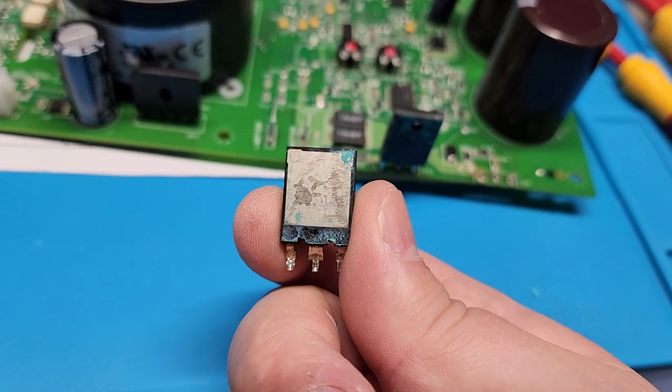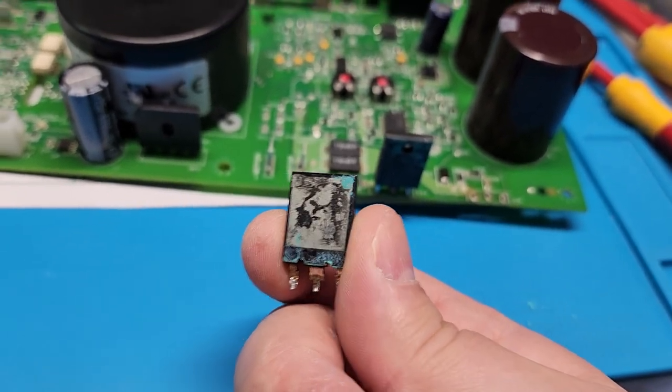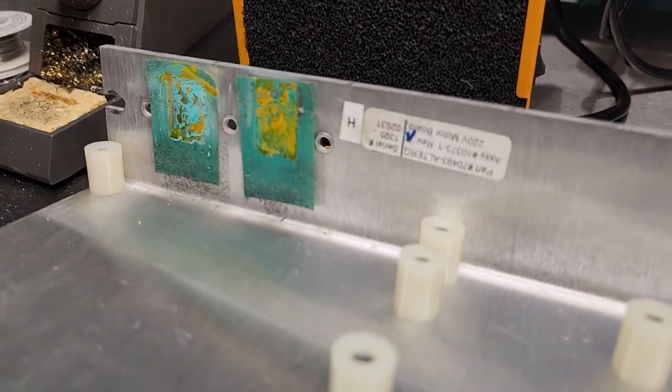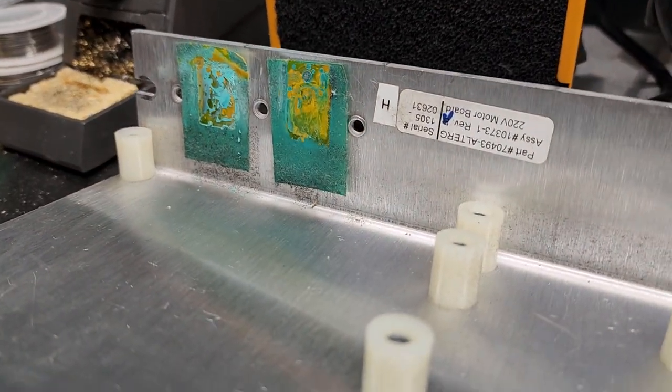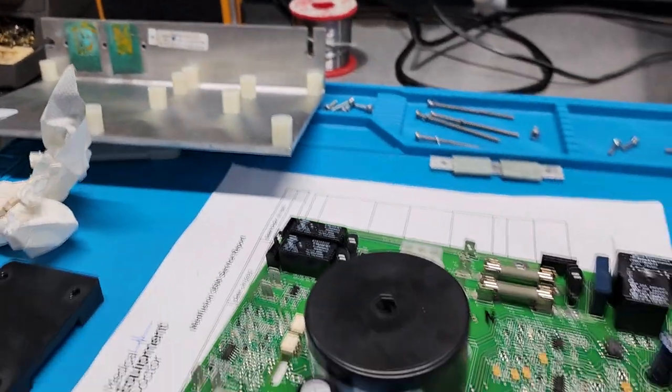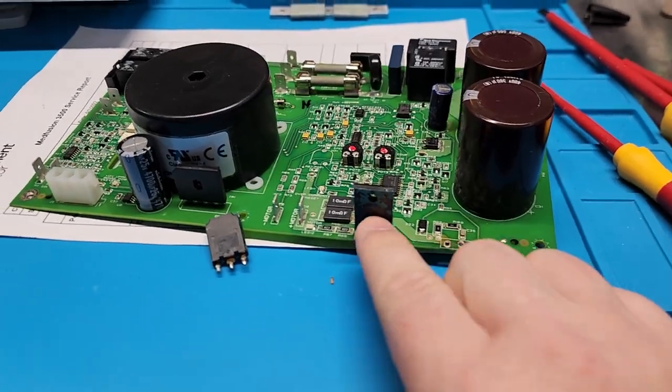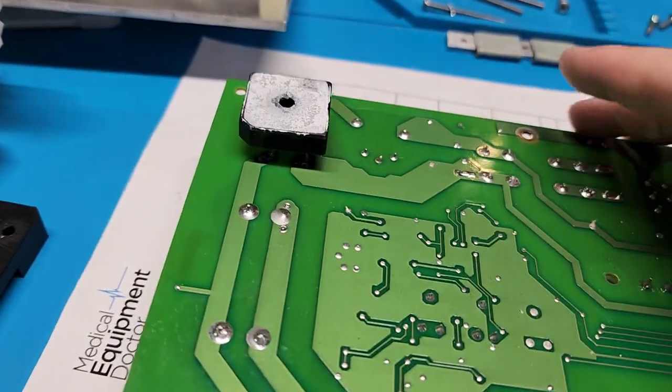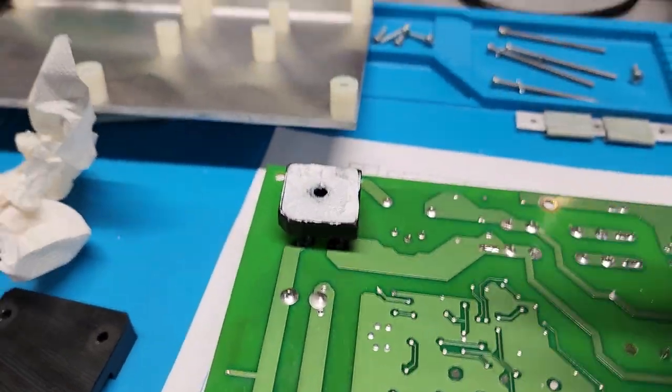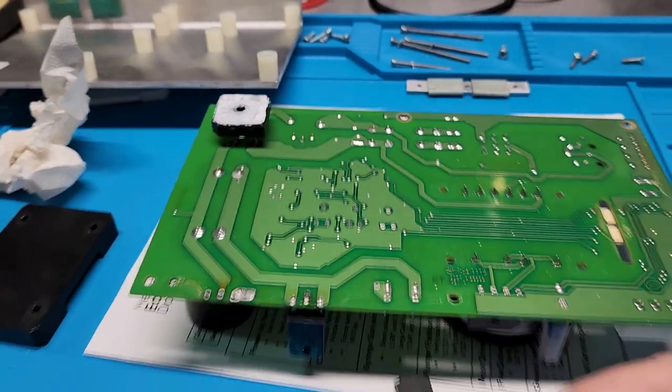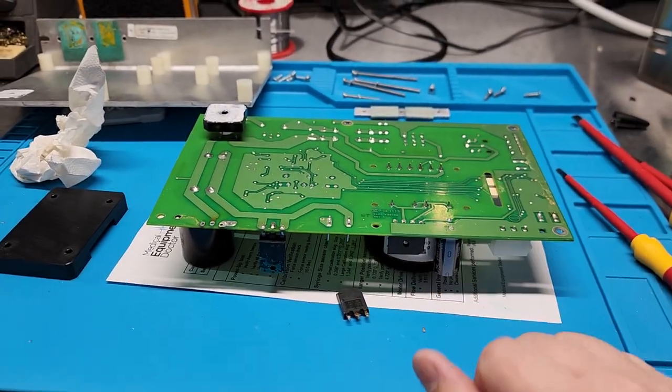Part of the reason that he probably went bad is overheating. So you can see my thermal compound on this guy. It is no bueno. So it's definitely got a problem. So we are going to replace this component. We are going to clean this guy, this guy, and my large bridge. There it is. See, I knew there's three bridges on this guy. And we're going to clean the thermal compound on this guy. And we're going to put it back together and should be good to go.